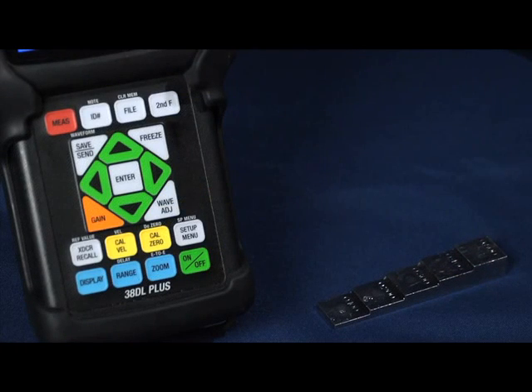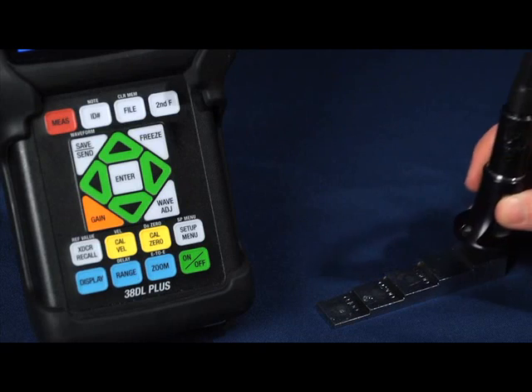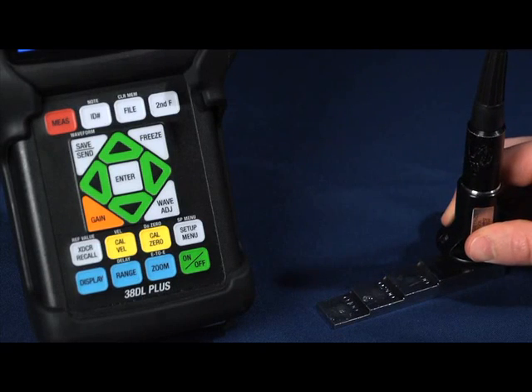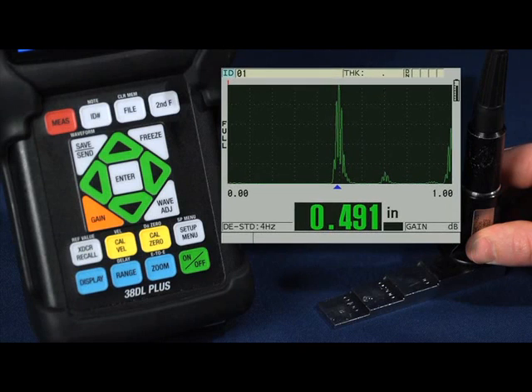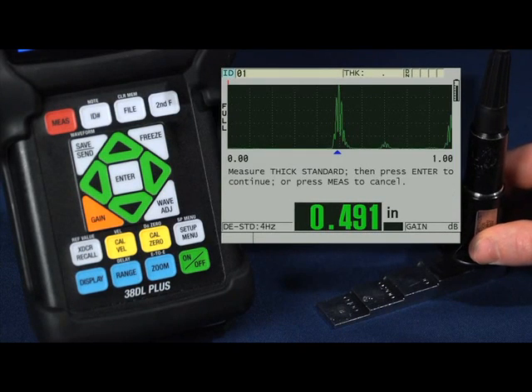Simply couple to your thick standard, in this case the five hundred thousandths step, and press the calvel key. Once we have a steady reading, press the enter key.